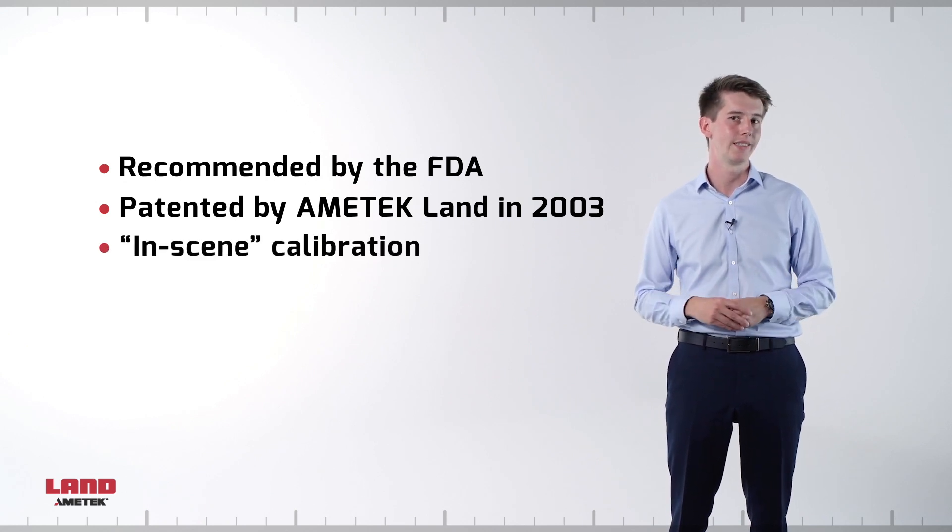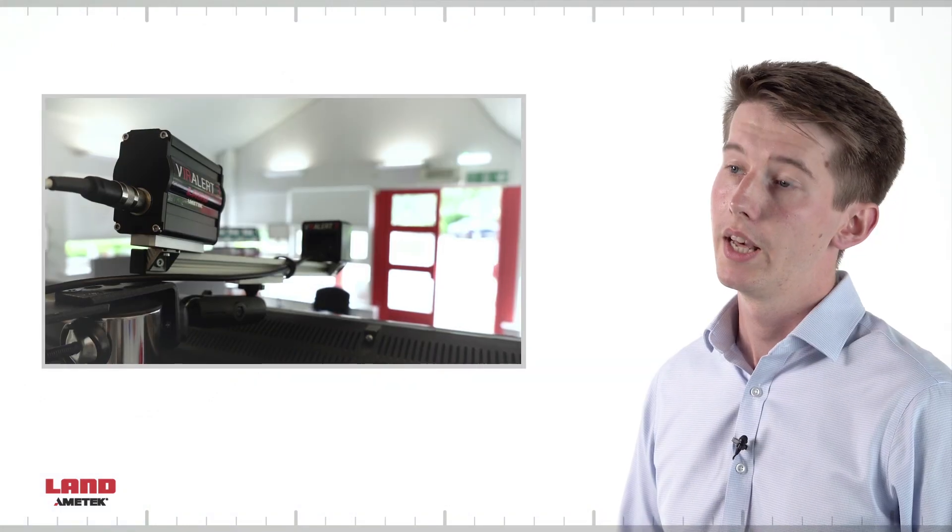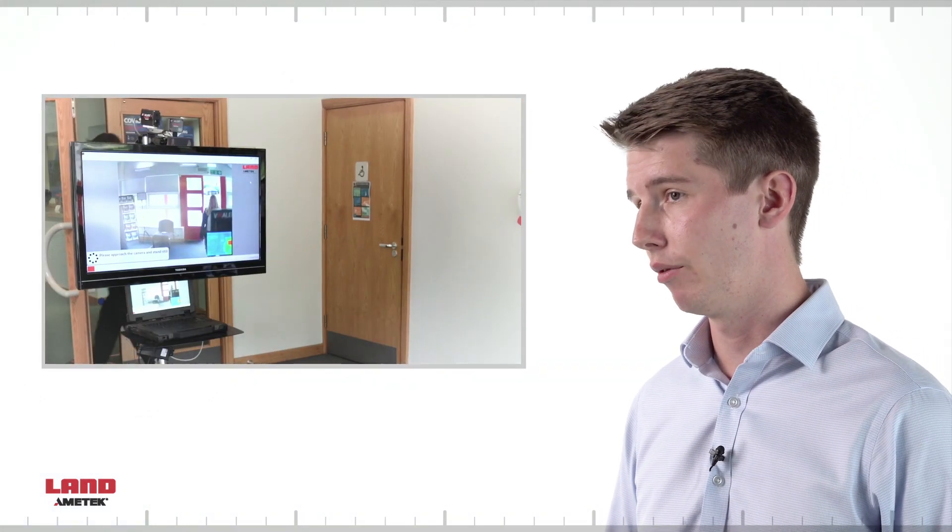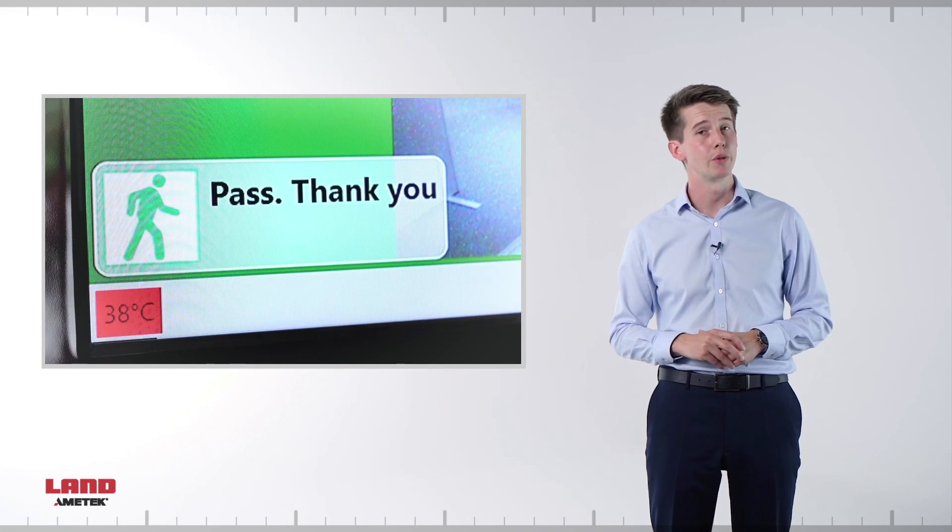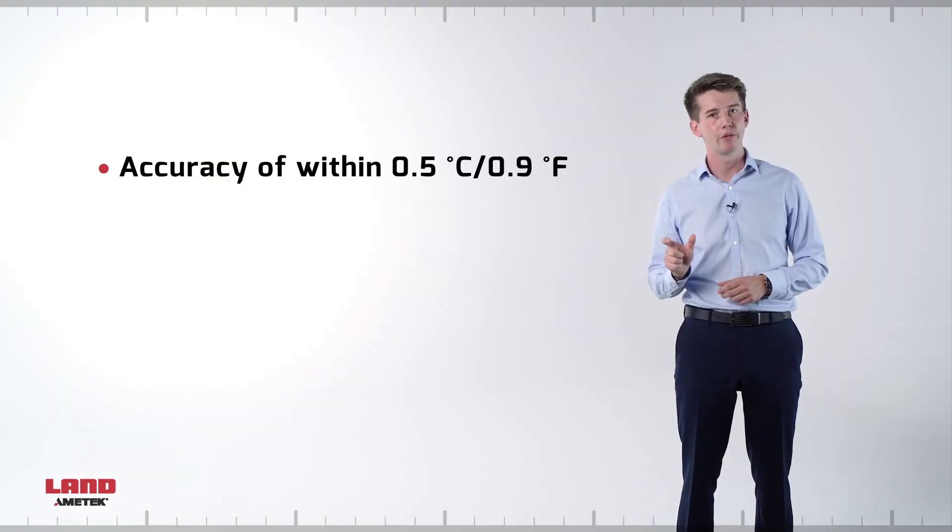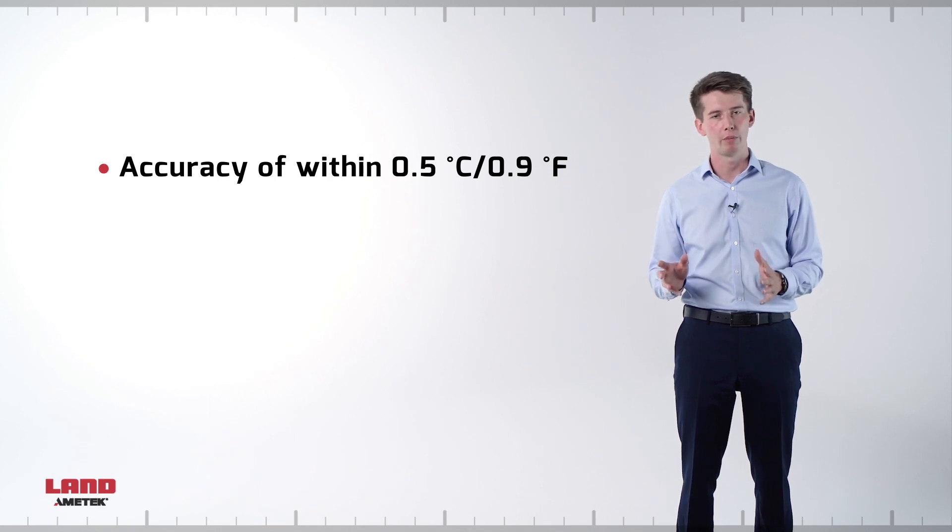It's also known as in-scene calibration. The black body provides a highly accurate reference source in the field of view of the camera. This enables the system to overcome the accuracy challenges associated with thermal imaging when measuring temperatures. This is achieved using a feedback loop and software algorithms. It delivers accuracy to within half a degree Celsius or 0.9 degrees Fahrenheit in real world applications and conditions.